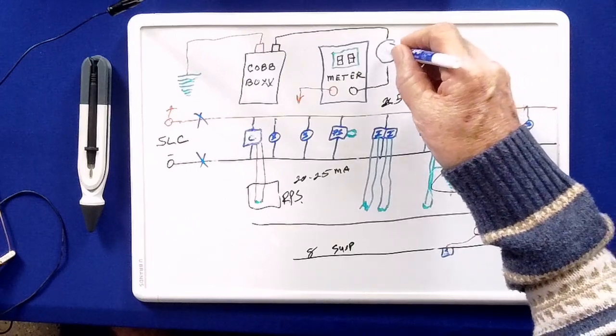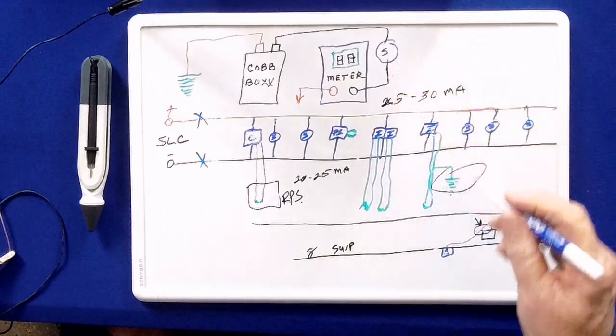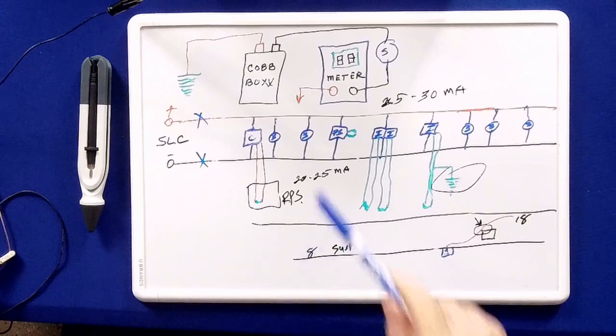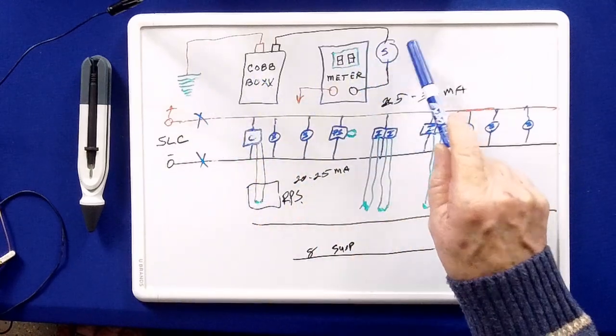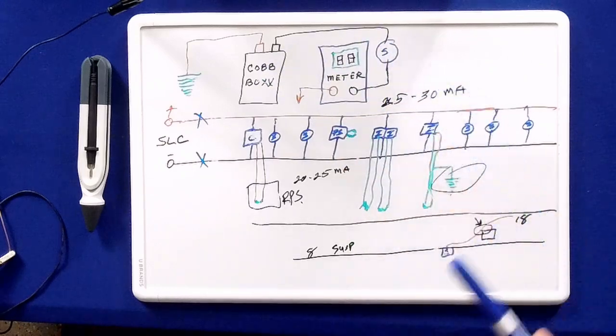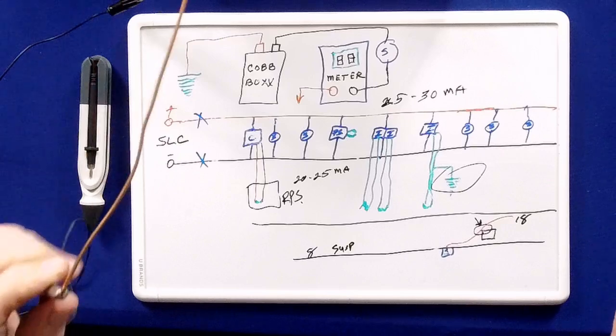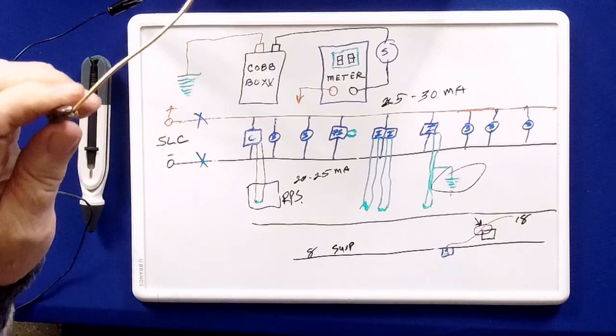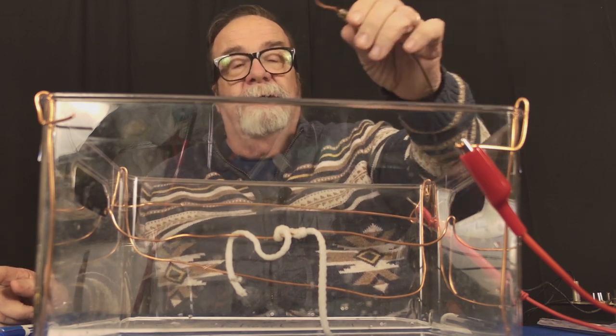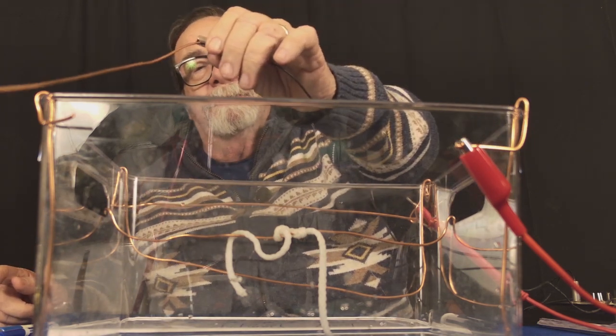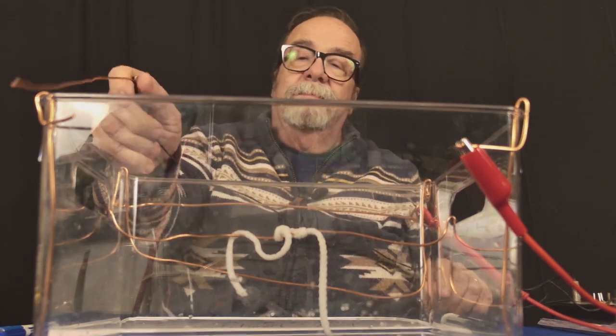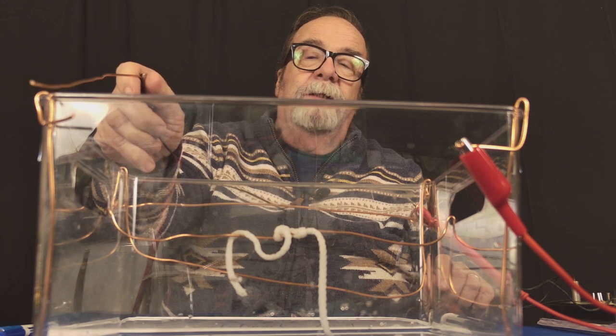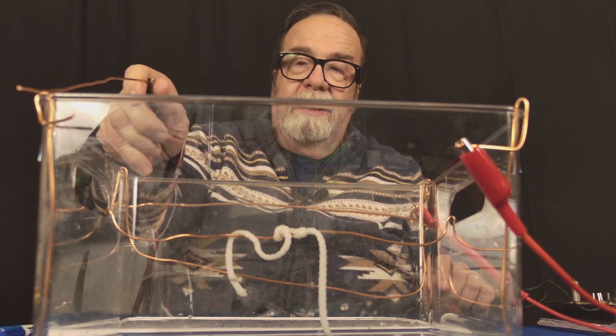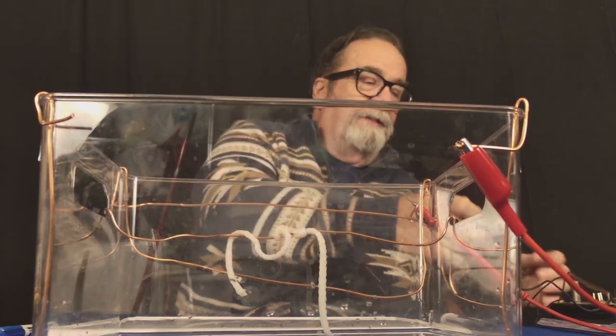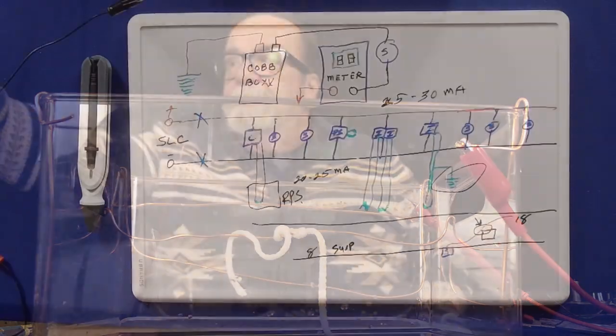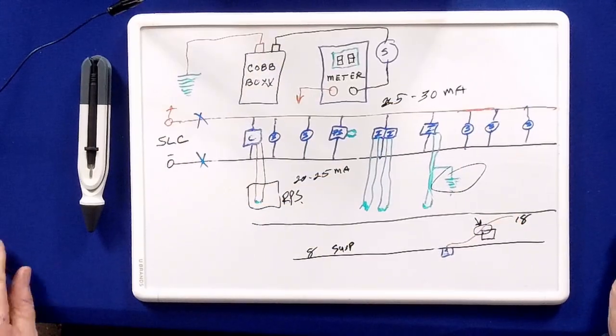Get yourself a piezo, Sonalert, a beeper. Put it in series with this. So now you've got the Cobb Boxx, the meter, the Sonalert, all in series. This is polarity sensitive. And I'm going to show you real quick here with a wire on the box here, and I want you to listen carefully, because if this grounds, you can hear it vibrating and going off. And that's what you're going to hear if you've got a vibration ground out there in the field. So, having said that, this is what I found, and this is how I found it.